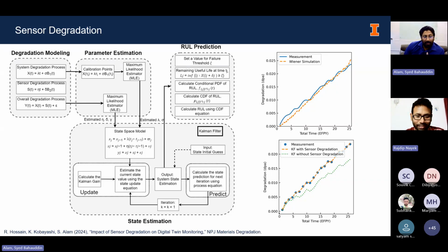I didn't say that here, but it has been done for a real nuclear power plant case. In Missouri, there's a power plant, Ameren. Fortunately we got some data, and they didn't have explicit sensor degradation data, but they had some thermocouples, which are a kind of sensor. They had the degraded thermocouples, and that was the benchmarked information we used, because the journal wanted some trust in the model itself. So that's what we did.